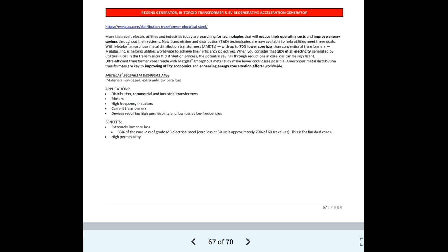With the Metglas amorphous metal distribution transformer, AMDT, with up to 70% lower core loss than conventional transformers, Metglas, Inc. is helping utilities worldwide to achieve their efficiency objectives. When you consider that 10% of all electricity generated by utilities is lost in the transmission and distribution process, the potential savings through reduction in core loss can be significant. Ultra-efficient transformer cores made with Metglas amorphous metal alloy make lower core losses possible. Amorphous metal distribution transformers are key to improving utility economics and enhancing energy conservation efforts worldwide.